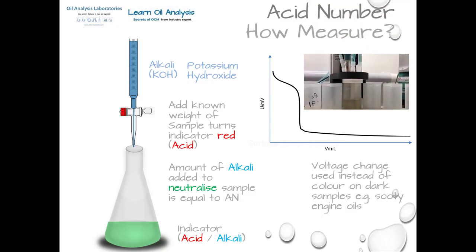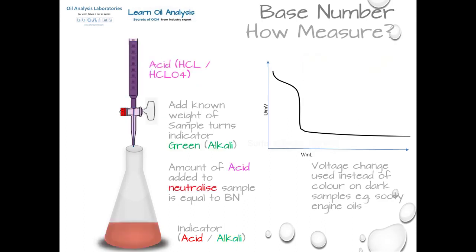On dark oils we cannot use colour, so we use voltage change — called potentiometric titration. To measure the base number, we simply switch the solution and titrate with acid, but still use the units of milligrams of KOH per gram to allow for direct comparison of measurements.